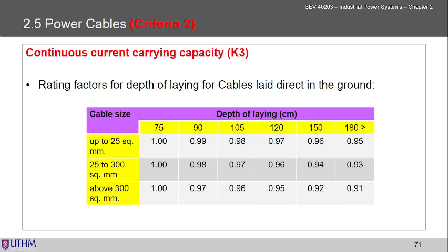Okay, and it depends much on the cable size, so this cable size is up to 25 square mm and above 300 square mm. This is the depth of laying in centimeters, 75 up to more than 180 centimeters, which is very deep inside. Okay, and then you can see the K3 value here.